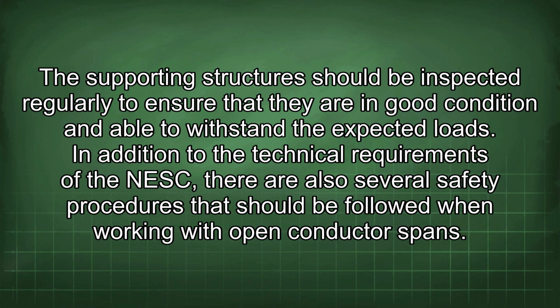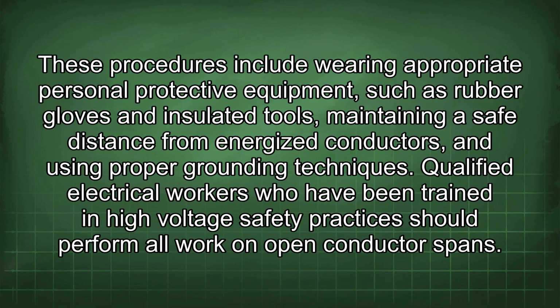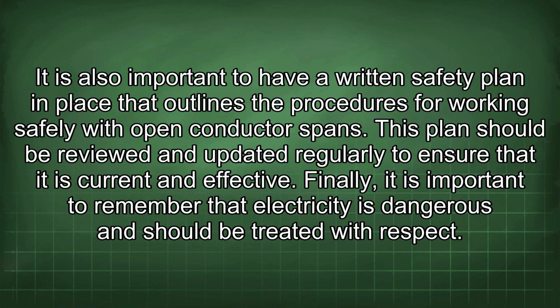In addition to the technical requirements of the NESC, there are also several safety procedures that should be followed when working with open conductor spans. These procedures include wearing appropriate personal protective equipment such as rubber gloves and insulated tools, maintaining a safe distance from energized conductors, and using proper grounding techniques. Qualified electrical workers who have been trained in high voltage safety practices should perform all work on open conductor spans. It is also important to have a written safety plan in place that outlines the procedures for working safely with open conductor spans. This plan should be reviewed and updated regularly to ensure that it is current and effective.